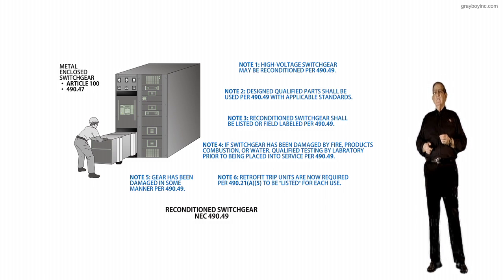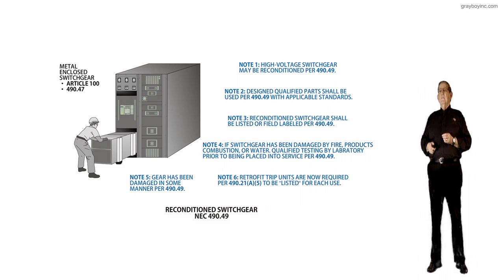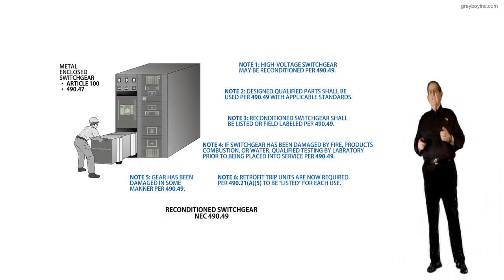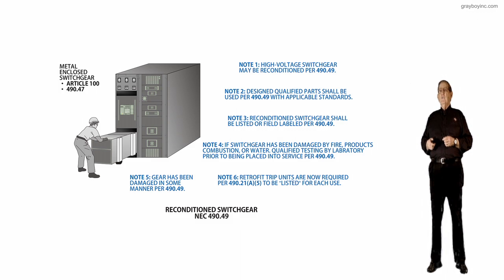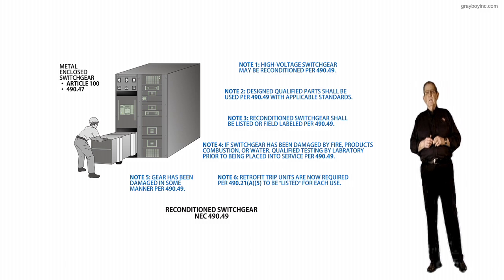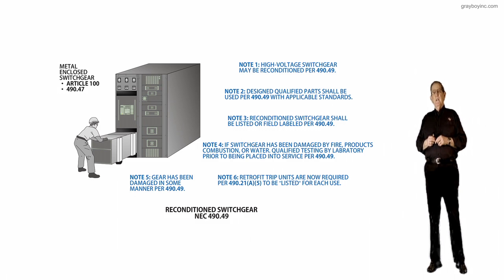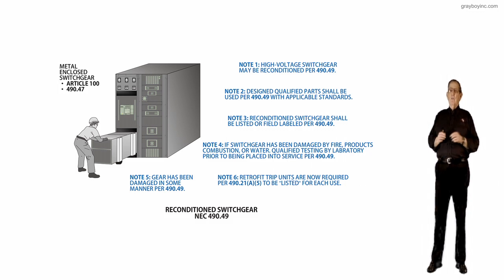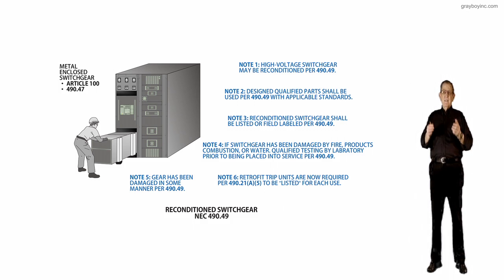And of course, note 6 is that retrofit trip units that are retrofitted and can be used are now required as outlined in 490.21A5, which would deal with fuses, circuit breakers, and so forth, if you're looking at A or B, to be listed for such use. So in other words, we just couldn't go pick up a retrofit kit and use it if it wasn't listed for such use. Now, the old markings and labeling would be removed, and you would put the new ones on if you recondition it. So this gives you a good summary of this new section and what is required when you're dealing with reconditioned switchgear in accordance with 490.49.